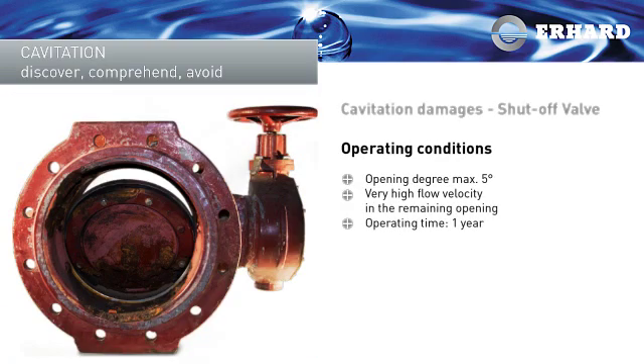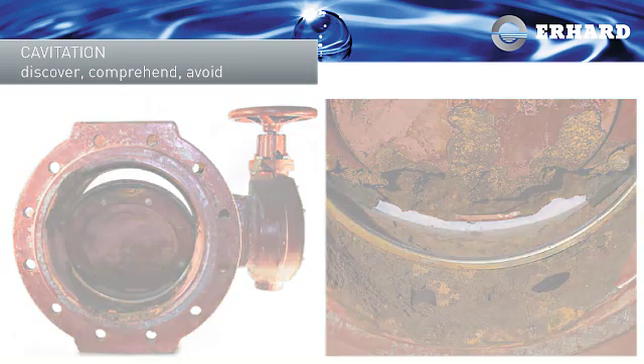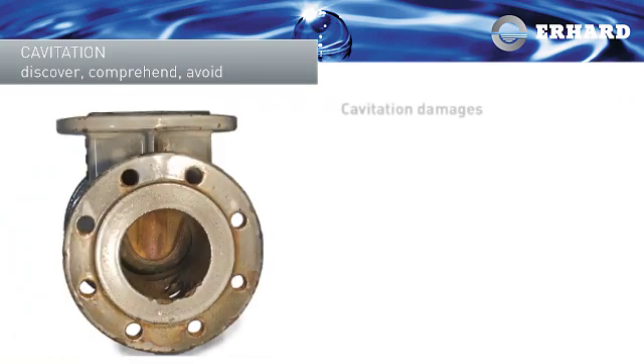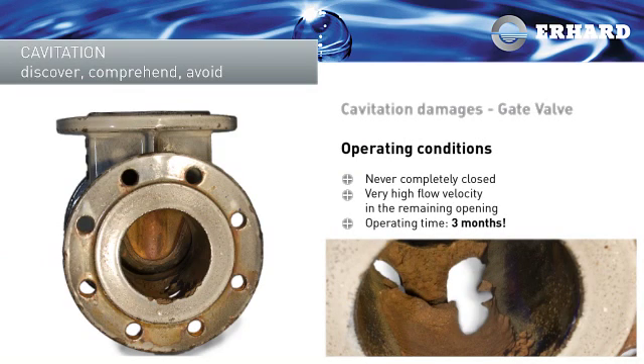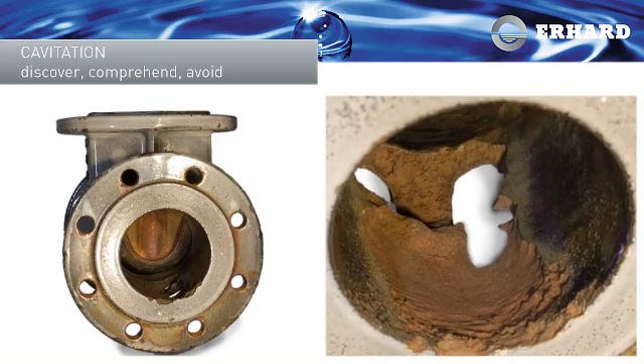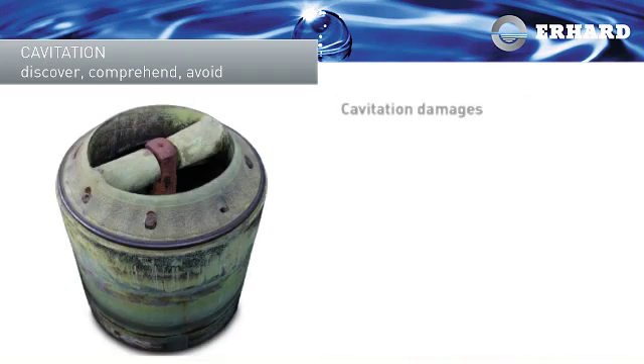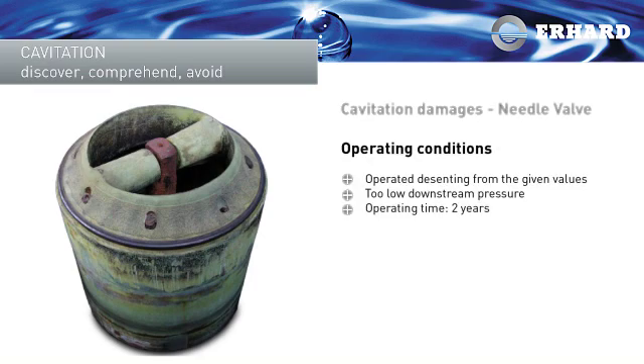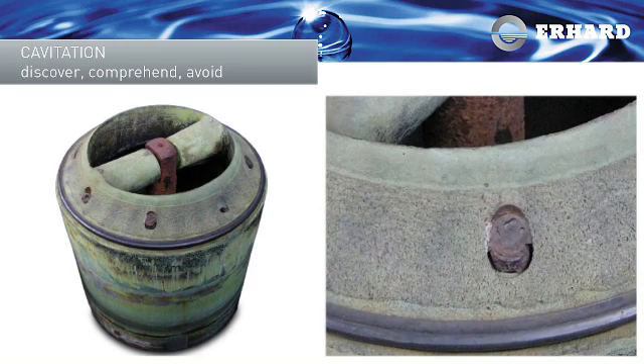Cavitation damage to a shut-off valve used as a control valve — the valve had to be replaced after only a year. This gate valve, which was never completely closed, reached the end of its life after only three months. Cavitation can also occur in control valves if they are used under operating conditions different to those of their design.